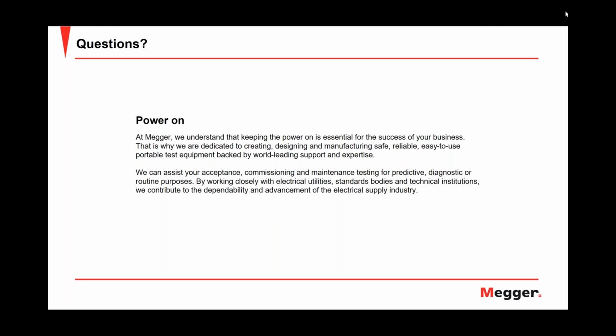And depending on your equipment, more modern equipment has this insulation resistance function built in, even in an automated way. So if you connect your 3 cores, you can measure actually all 6 pairs, the 3 phases to the neutral and the 3 phase-to-phase situations at once, and you get in a few seconds a very clear picture of what's going on. So that is one thing. So phase comparison can be used.